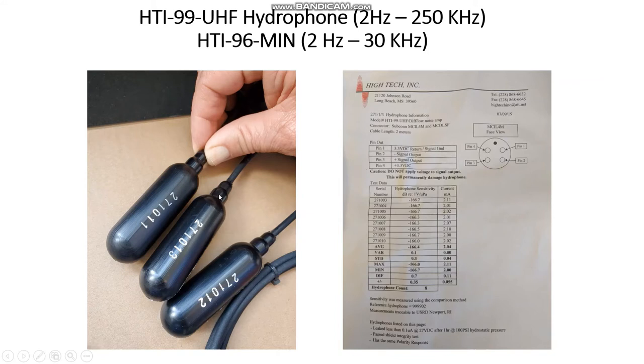Which free field cable hydrophones do we have available right now? Right now we provide or support the hydrophones that are manufactured by HTI, and you would buy them through Desert Star. They are connected to our specifications and programmed. Their preamp is programmed to our specification. You do get a calibration sheet that gives you the sensitivity for each individual unit that you receive.